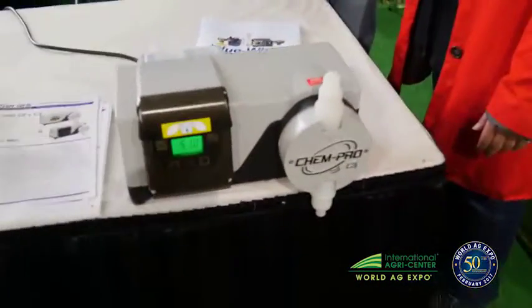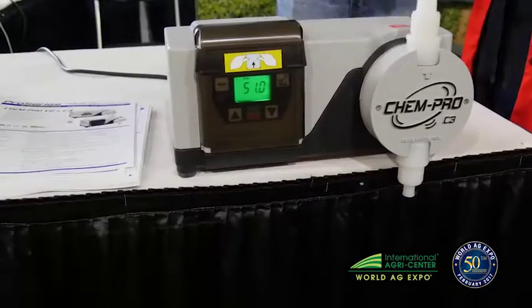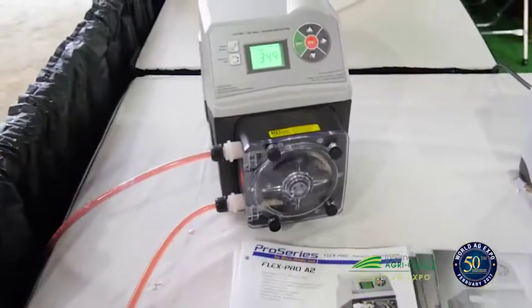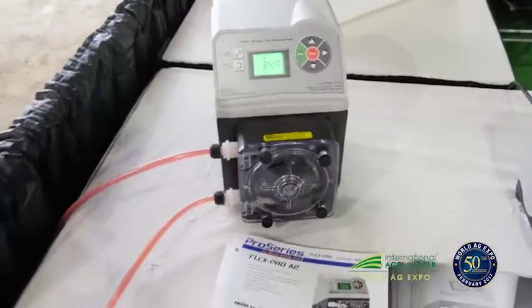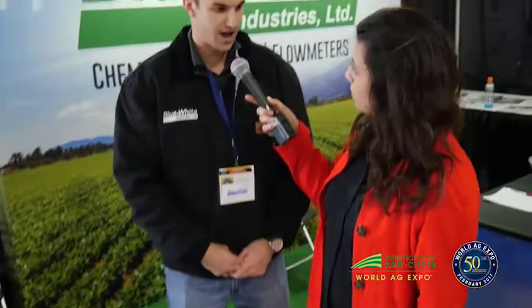You have brought a few of your products with us. Can you go over what you have here? So this one here is our diaphragm metering pump for higher pressure applications — up to 175 PSI — so this is really common for fertilizer. We have our C2 and C3 series, and the farther one over there is our peristaltic metering pump. That one is used in a wide variety of applications, from industrial wastewater treatment to municipal. It's typically used for low pressure applications, like chlorine that has gas buildup that you don't want in a diaphragm pump.